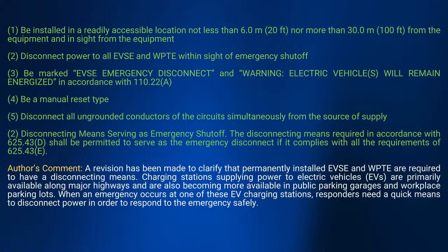It's installed in a readily accessible location, not less than 20 foot but not over 100 foot from the equipment, and it's in sight from the equipment.